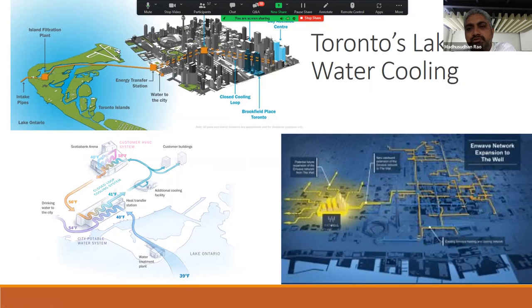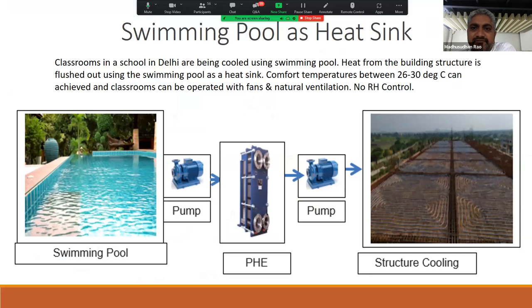But in our case, we can use it in two ways. One, as a condenser for the chiller to have better efficiency and not have to do treatment of water and all that. The other could be to combine this with structure cooling and use it. And that is what we are doing in one of the projects. I'll show you. As a first step, this is a school project in Delhi where we're using a swimming pool as a heat sink. We're not using any refrigeration equipment, no compressor-based system, just a plate heat exchanger to flush the heat out from the building structure, so that we don't even need a cooling tower, maintenance of a cooling tower and all that.